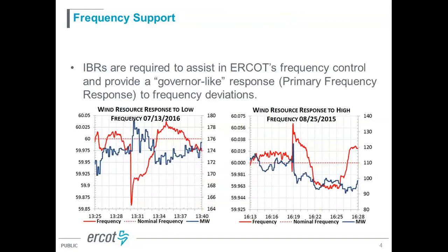From the frequency perspective, IBRs connected to ERCOT are also required to provide frequency support. The expectation and requirement is very similar to a typical synchronous machine, providing a governor-like response. The one on the left is an example for low frequency, where a wind resource increases power during the low frequency event. The one on the right is the other way: when we have a high frequency, the IBRs are required and capable to reduce the output to help the frequency recovery.